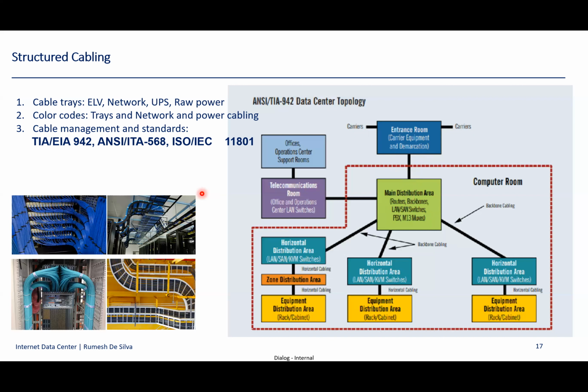And once you are doing cabling, patch panel implementation, and splicing inside the data center, you have to be aware of the bending radiuses. Also, after laying cables, you have to get a report by using Fluke or any reputed calibrated machine. You have to use calibrated meters for that.